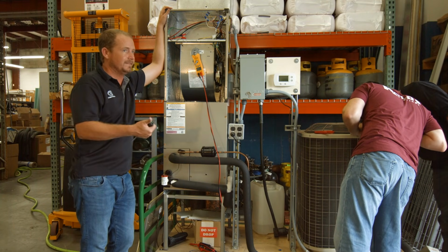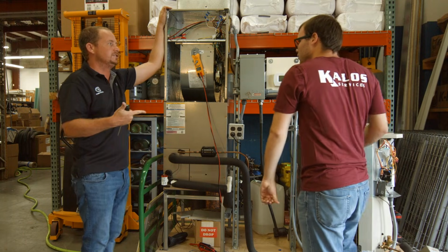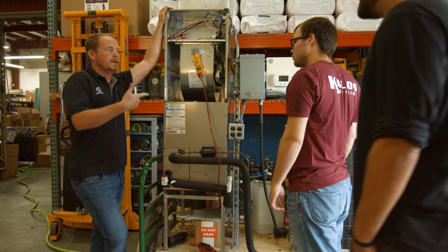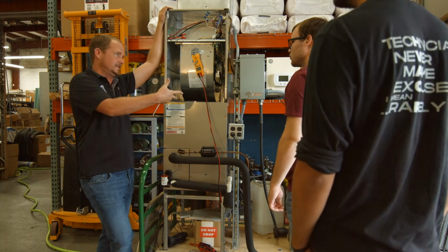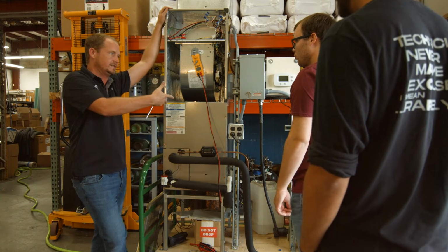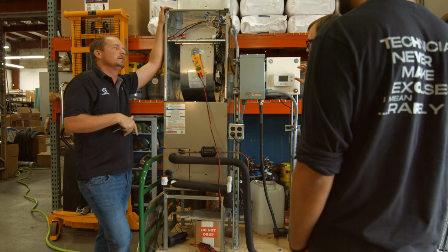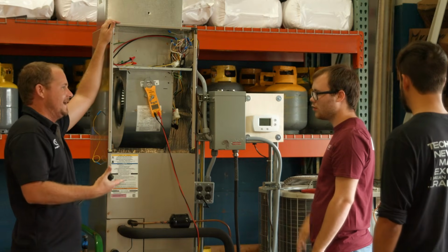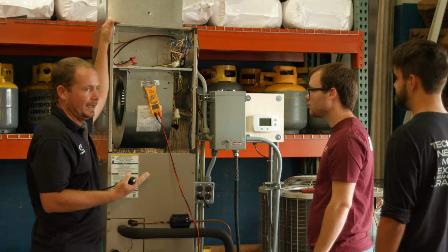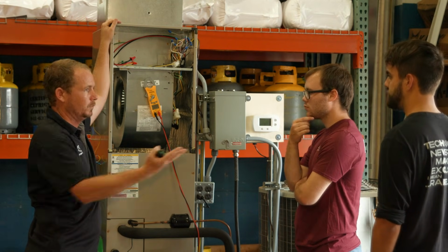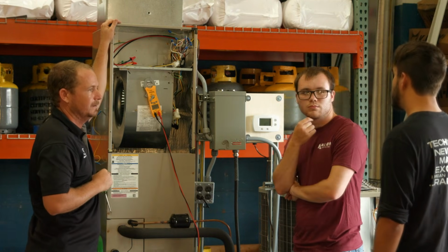All right, so you've identified the reversing valve, you've identified it's attached. I would probably go through, if we hadn't already just done it, and check the thermostat settings next to make sure that the installer setup is set up properly. We know we checked it earlier, it's at the 5. We just did that, so we're not going to go through that again, but that would be the next thing I would probably check. What are some other things? What would you do next, Eli?